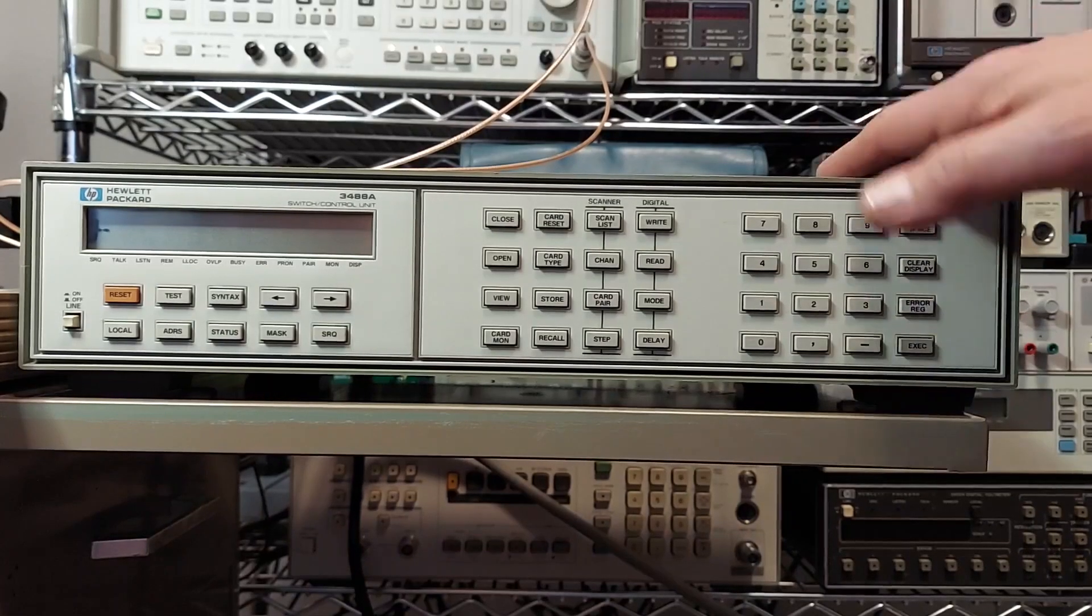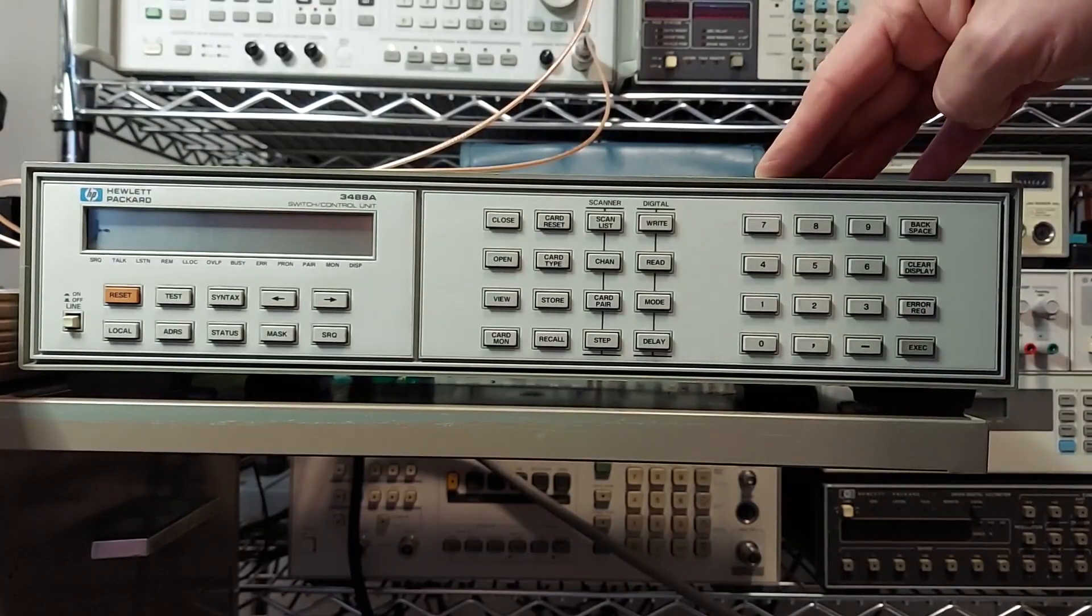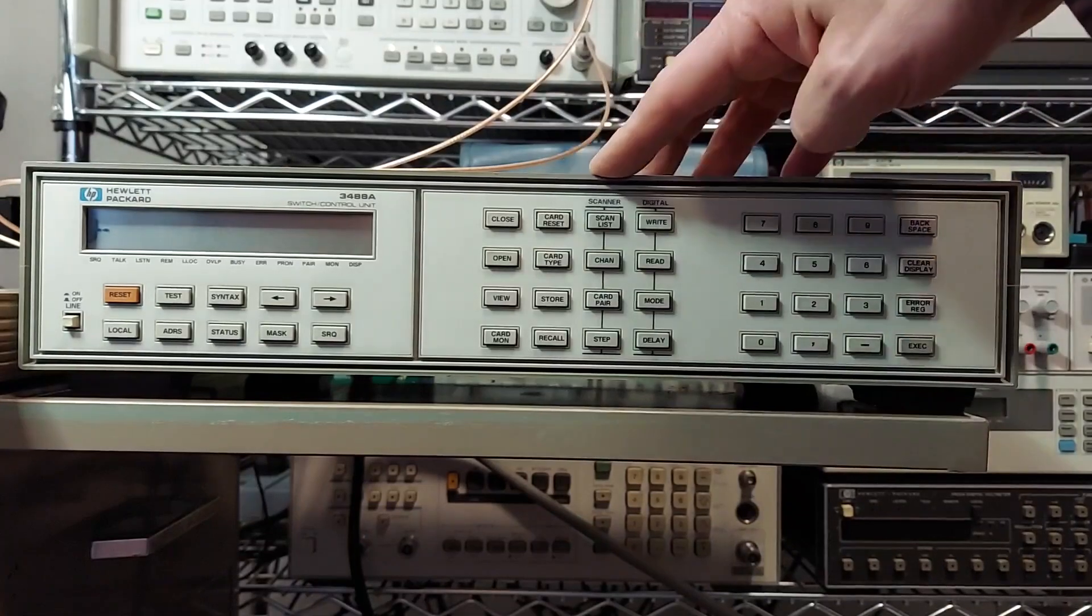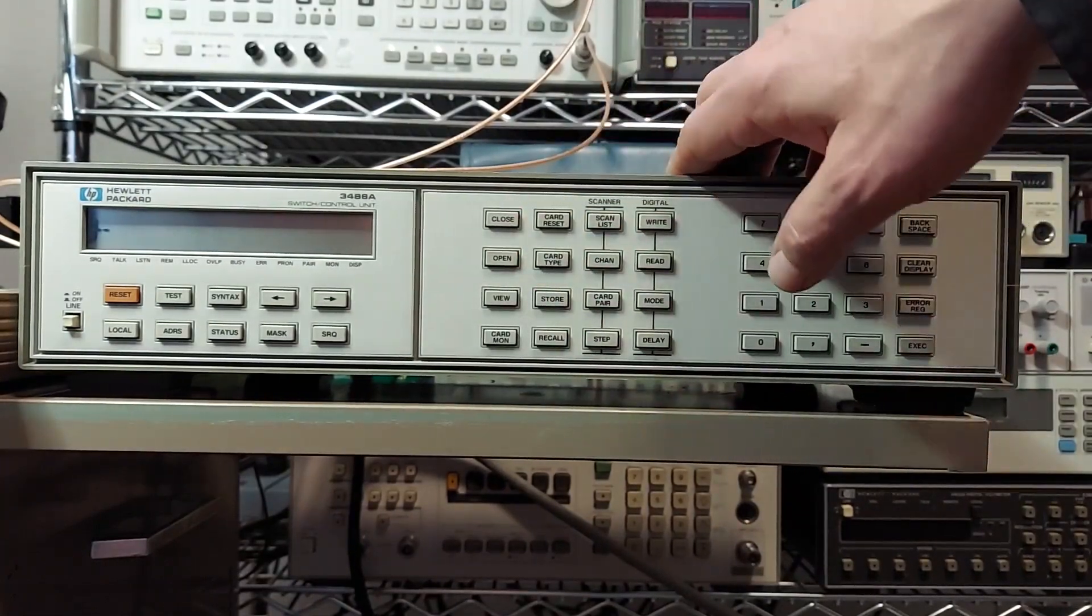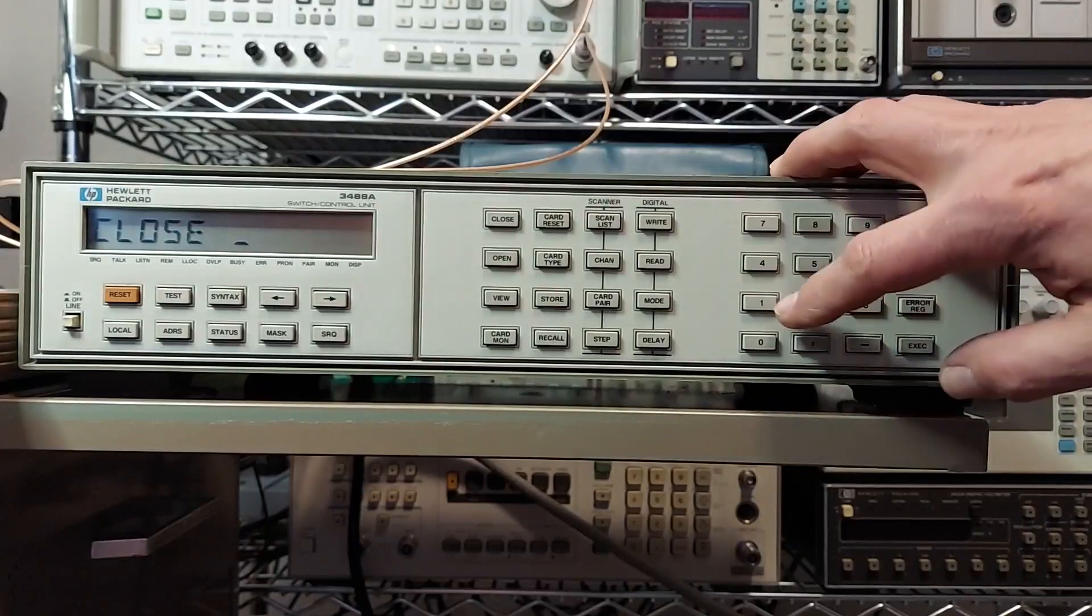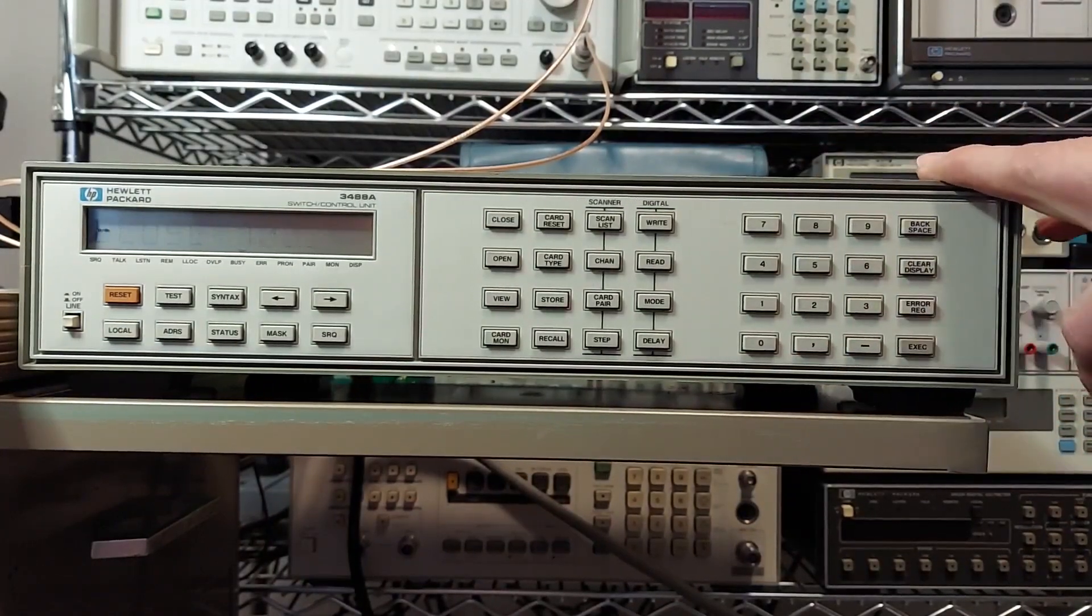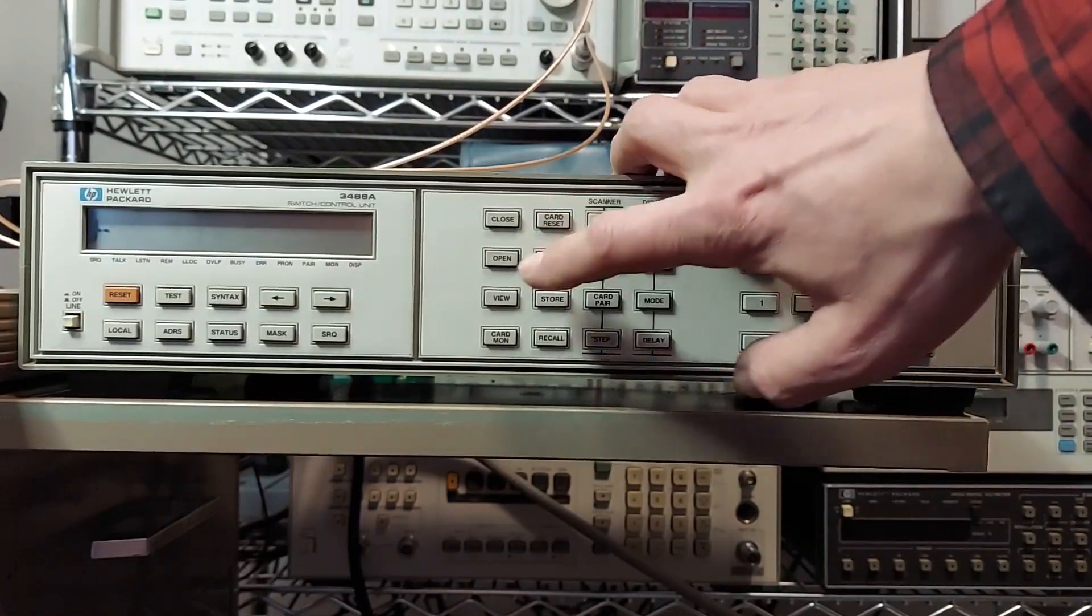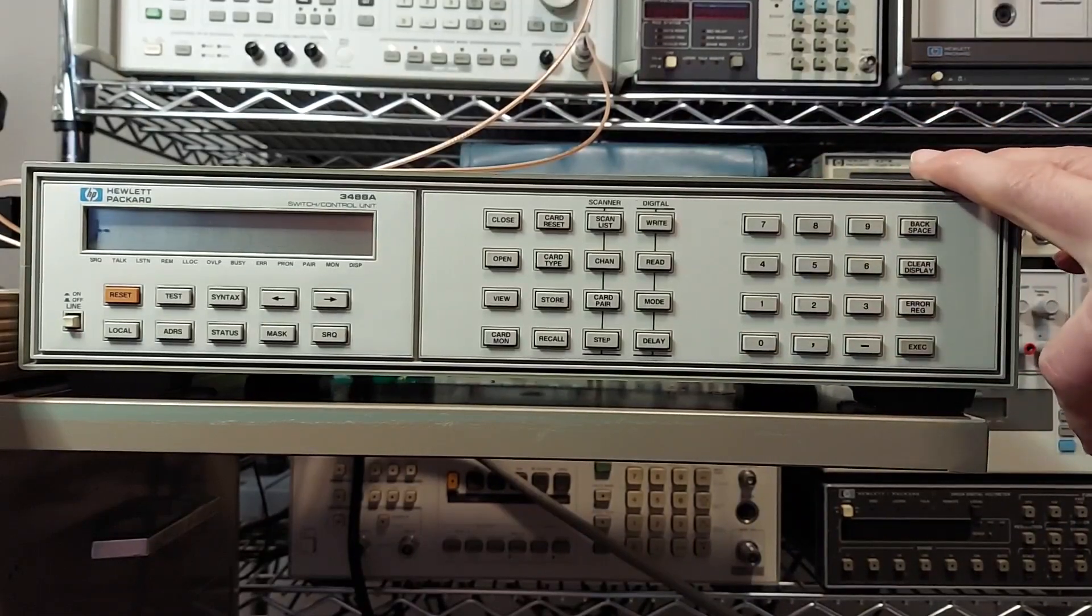Okay, we got it hooked up here. I want to kind of go through some of the cool functions this thing does. In order to open or close a contact, we use these two buttons here. So if I wanted to close card one port 00, press the close button, card one port 00. And now that relay is closed. I want to open it, I do the same thing 100. Now it's open again.